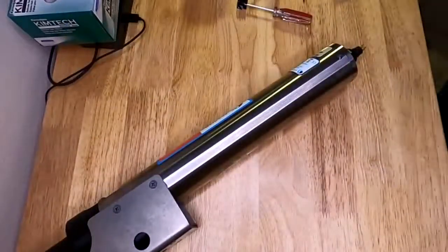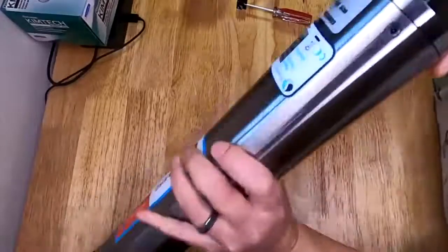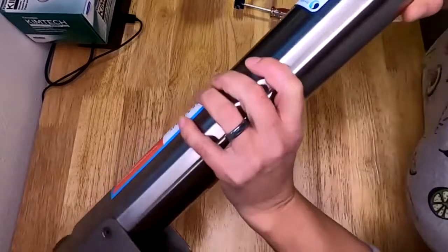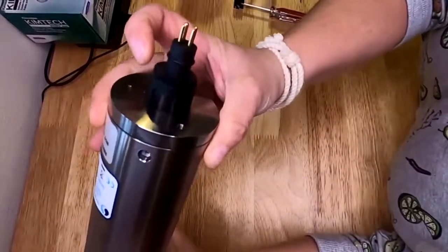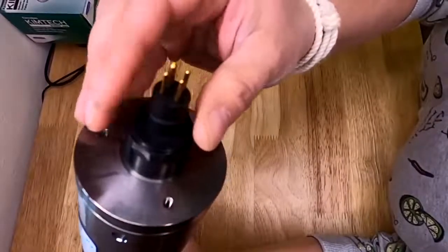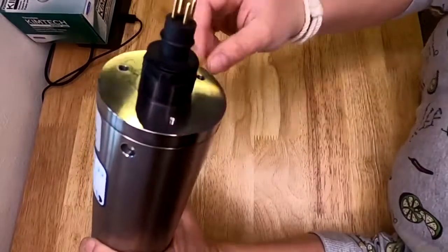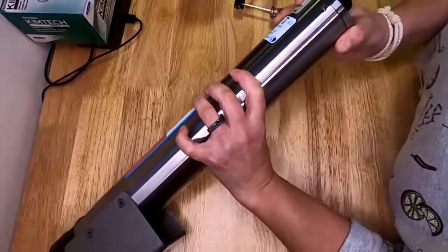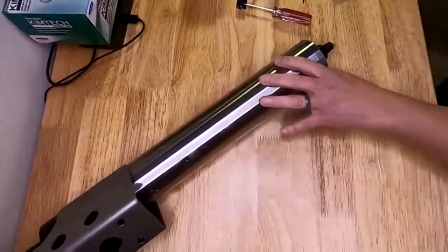Before I connect it, I do actually want to make sure that this is really nice and clean, and that you don't have any gunk on it, or anything that looks like corrosion. You can clean it off and use a little bit of the cable connector lubricant, which is DC4. You don't want to use anything with silicone because that will actually break down the rubber on this. But DC4 is what we recommend, and that's what you can use as well.